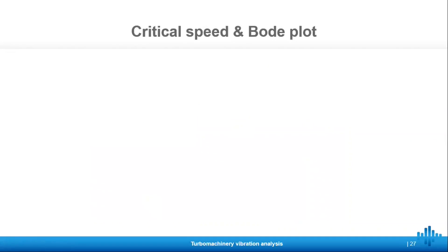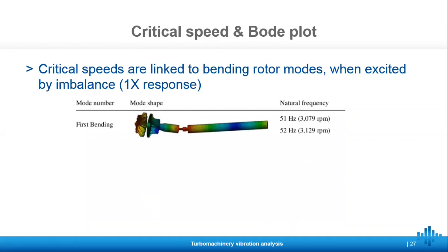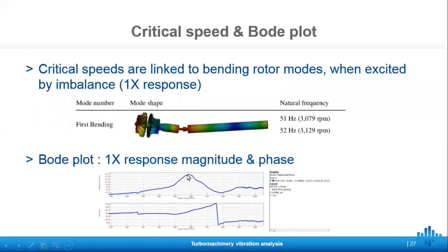Now let's take a look at the Bode plot. The 1x is a response to imbalance, and when this imbalance excites the first bending mode of the shaft, we will have a resonance. This resonance will be transduced by a critical speed during a run-up. For example here, we have a natural frequency very close to 50 Hz — it's the first bending mode, as you can see by the mode shape. The Bode plot shows both the magnitude and the phase, so we can check if the phase is rotating and if at the same time we see a resonance, meaning we have a critical speed linked to a bending mode.